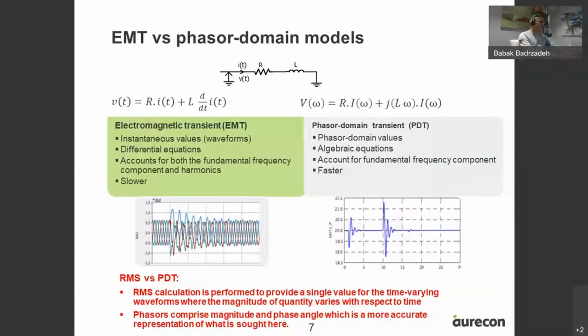Another difference is that EMT waveforms by default retain not just the fundamental frequency component but also harmonics and interharmonics, whether below or above the fundamental, even up to several kilohertz. Because of these two reasons—solving a differential equation, and retaining all these components—this type of modeling is slower. Phasor domain modeling, on the other hand, does not account for harmonics, and combined with solving phasor domain equations instead of differential equations, makes this type of simulation faster—sometimes much faster—depending on the size of the system and the level of detail included in the EMT model.